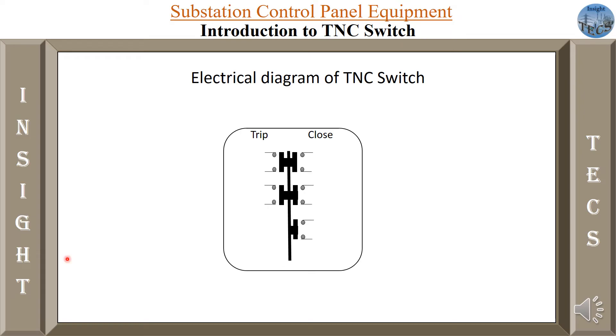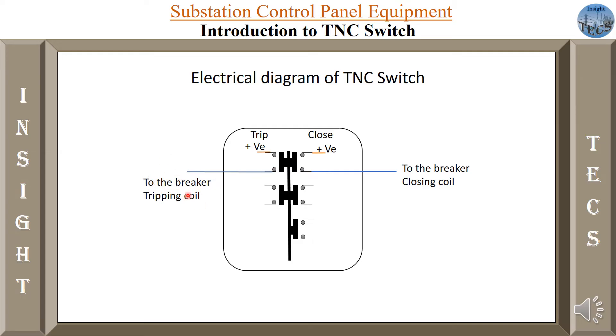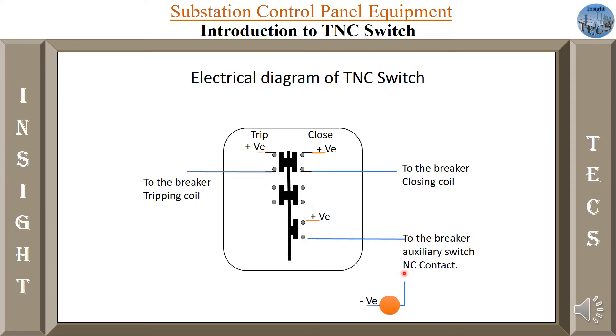Now let us move on towards the electrical diagram of the TNC switch. For the closed contacts, we provide a positive supply from the panel, and the other end is connected to the closing coil inside the circuit breaker. Similarly, for trip, positive supply is given to that contact from the panel, and the other end goes to the breaker tripping coil. Some wiring is also required for auto-reclose: we give positive supply at one end, and the other contact is connected to the auxiliary switch, which has one NC contact.